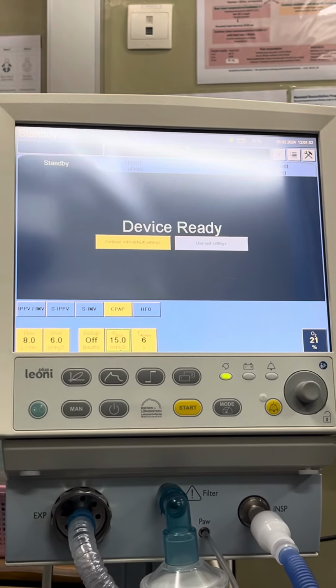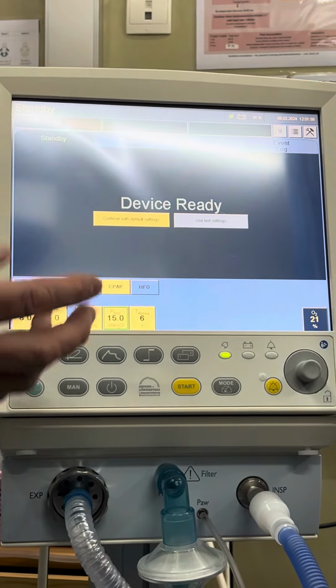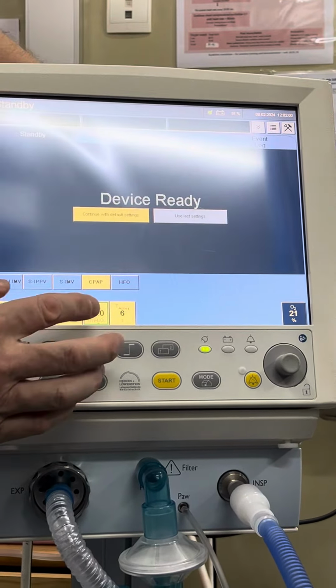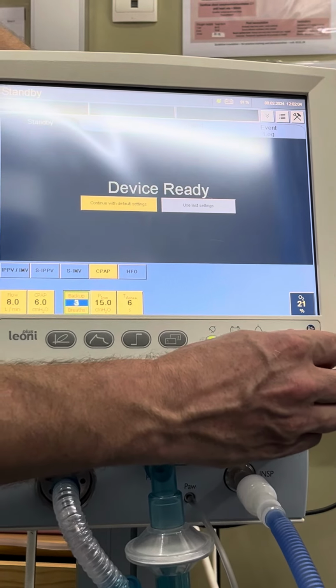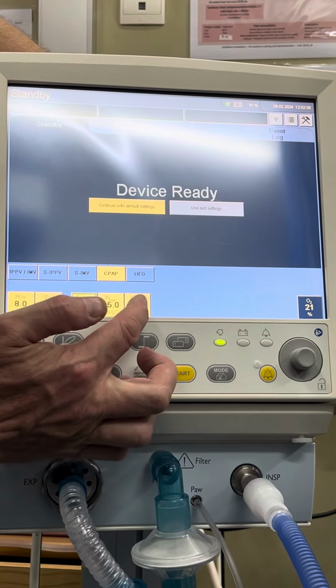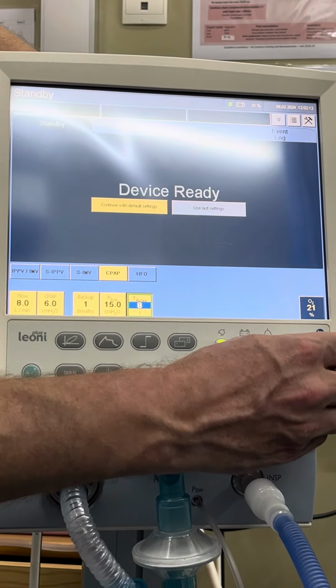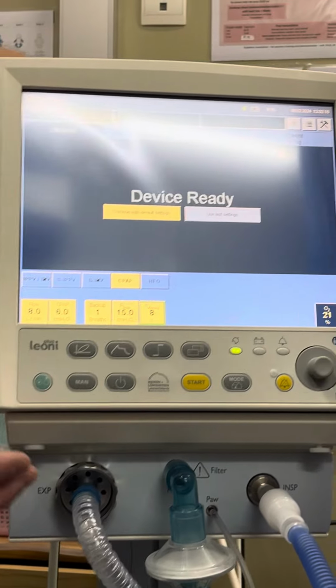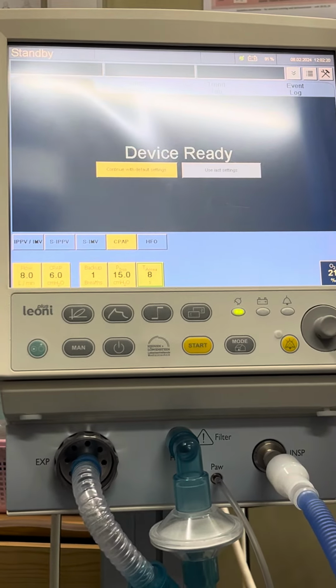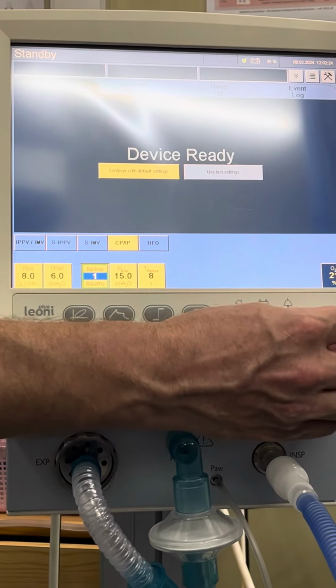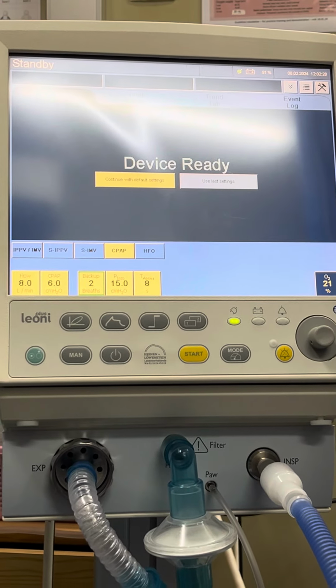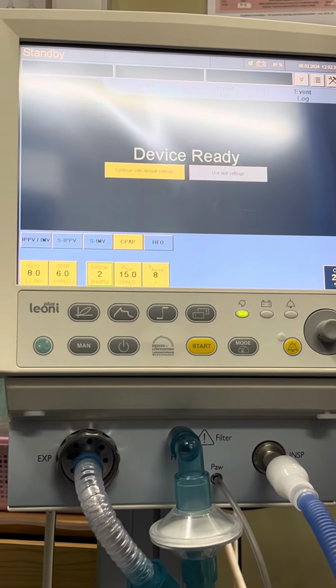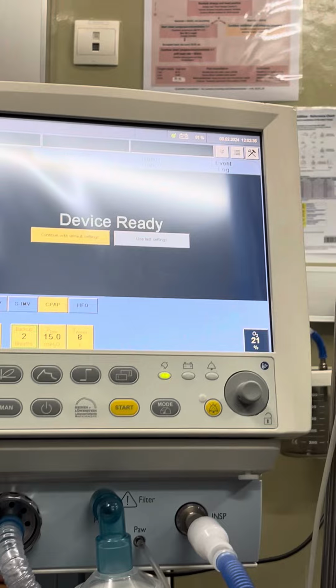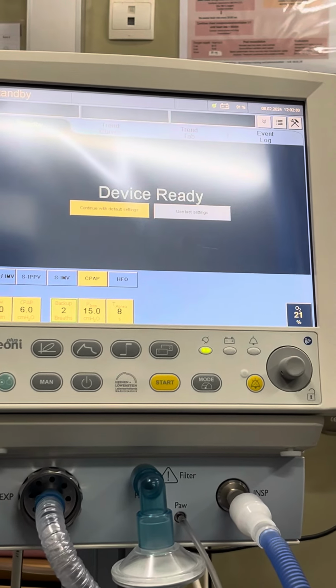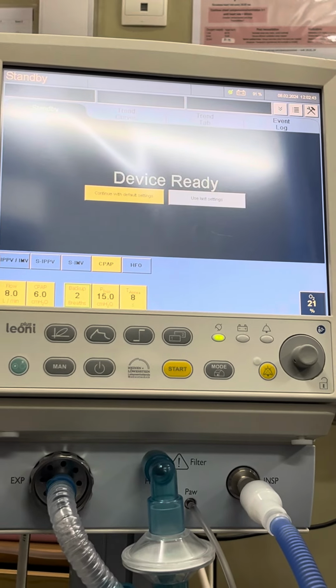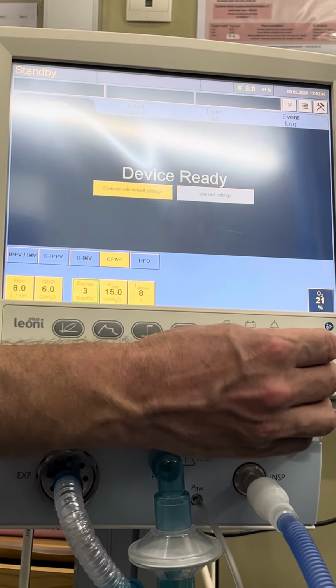So we will not do the CPAP right now, but if we had the tube sets, we could take off the flow sensor or leave it on, and then put on the backup. If the backup is 1, and if the apnea time is 6 seconds, let's turn it up to 8 seconds. Then after 8 seconds, the machine will give an extra backup once. If we turn here, it will give twice. It reminds the baby of breathing. If the baby's just not breathing, the machine will help the baby breathe again. So it's for an immature baby that needs some extra backups.